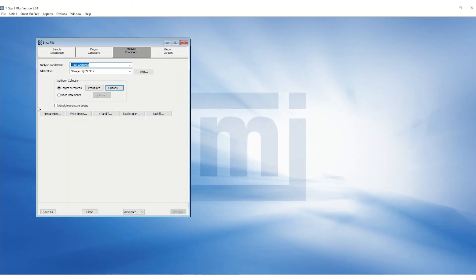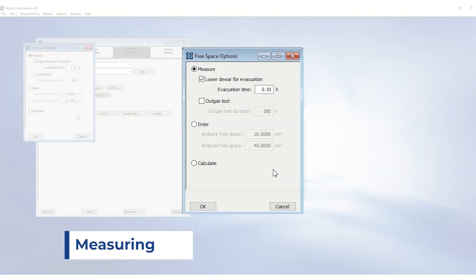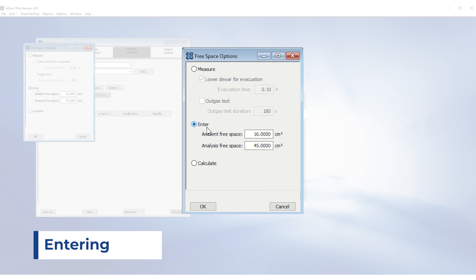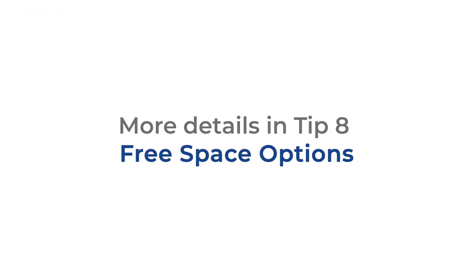Another way to optimize speed is by entering or calculating free space. Measuring the free space is the most accurate, but it is possible to obtain reasonable data without it. Entering the known value of free space requires a separate free space run, and calculating it requires the skeletal density of the material and a calibrated sample tube. This will be covered in more detail in tip number eight.